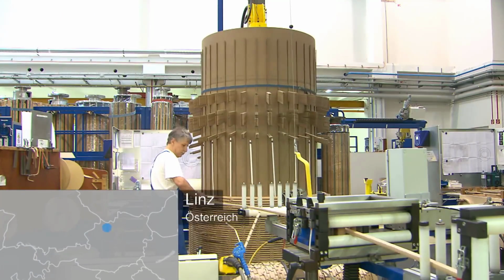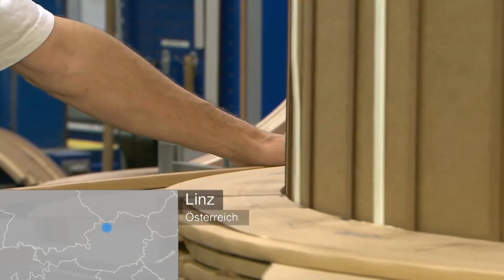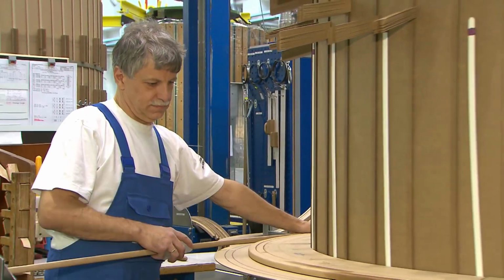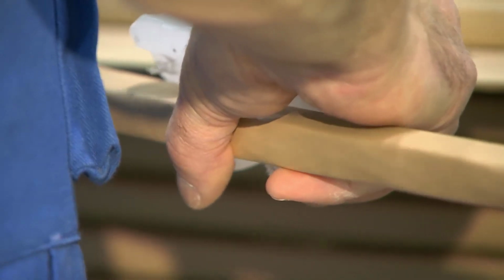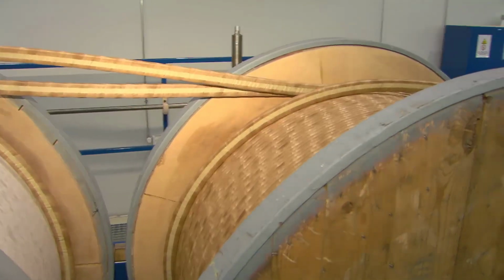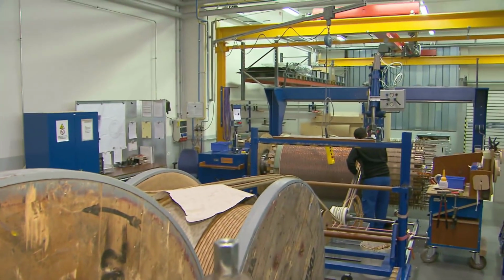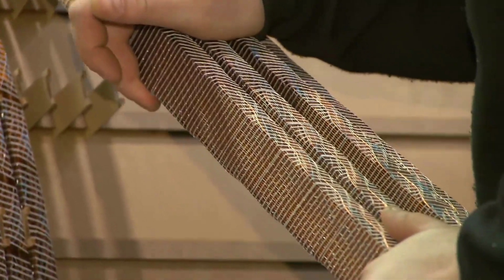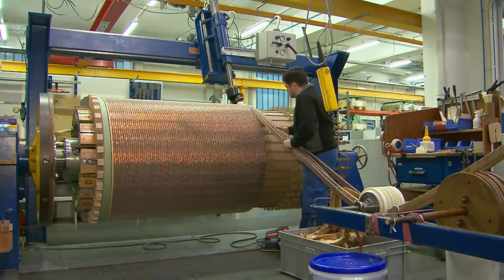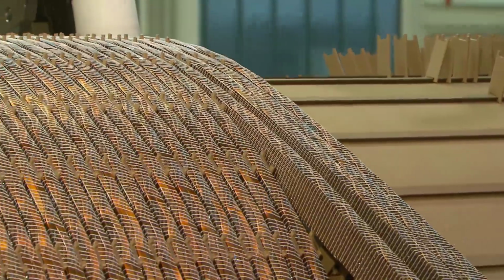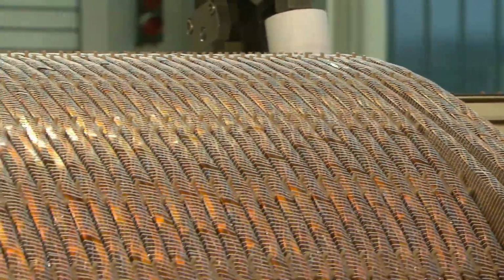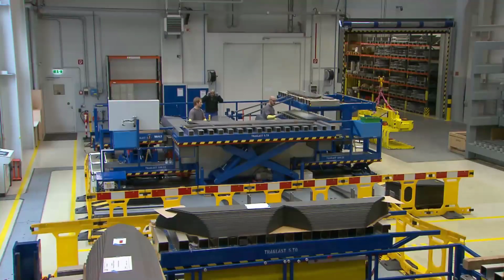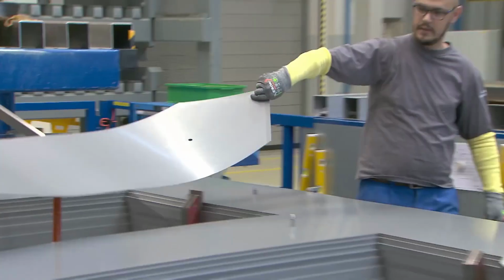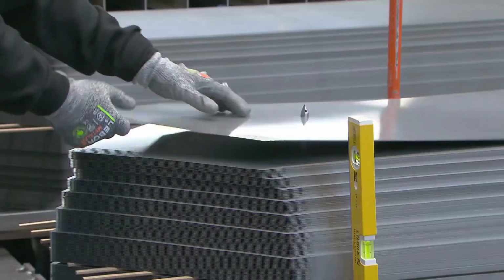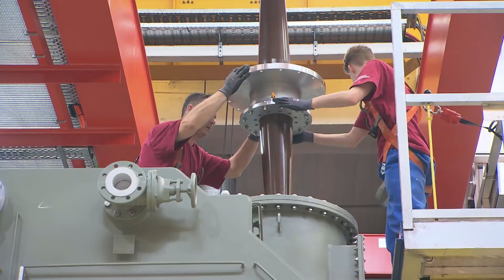For the Obervermuntwerk II, two machine transformers with a capacity of 200 megavolt-ampere were manufactured. First, the coils are wound, and the transformer core is manually stacked from thousands of individual sheets. Finally, the individual parts of the active part are assembled and lifted into the transformer vessel using a crane. The transformers, weighing 152 tons each empty without oil, are the heaviest individual components transported to the construction site. Extensive tests are conducted in the workshop before shipping.